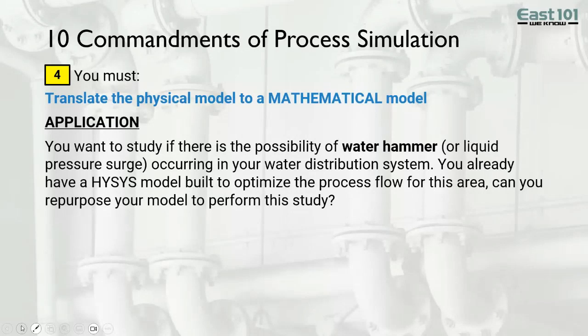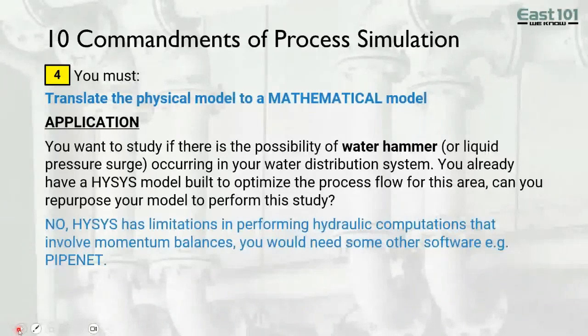So I was looking at this water hammer, or liquid pressure surge, in a system and tried using HYSYS dynamics - and was shocked that it didn't work. For a simple reason: it doesn't contain a sufficient momentum balance for a liquid, and it also doesn't take into account accurate liquid compressibility. So you can't model pressure waves within HYSYS, Unisim, or ICON. You need to use some other tool, like PipeNet or AFT Impulse, which is specifically built for liquid pressure surge computations.